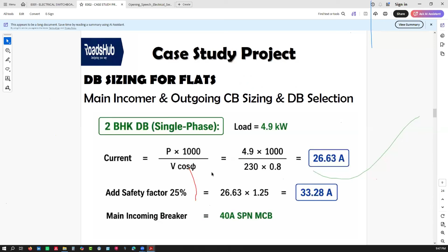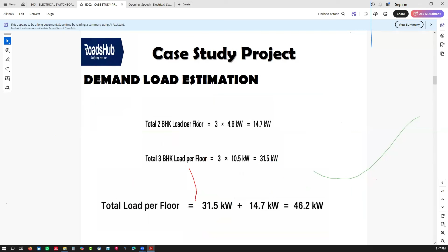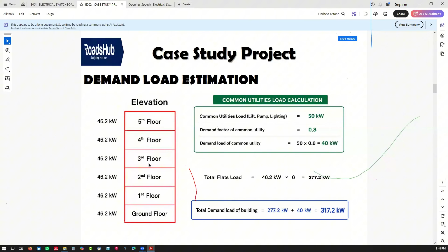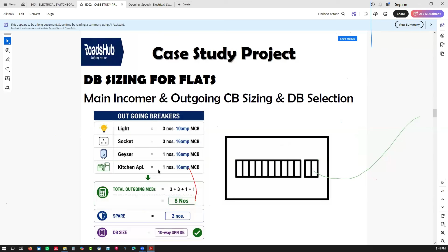So if I go now into the calculation of SMDB, simple. You need to know each floor is utilizing how much power. So you have 46.2 kilowatt per floor. And actually that's what we got here. 46.2 for each floor. So you need to design an SMDB for this floor, because remember you have first and fifth. They're actually far away from each other. You don't need a switchboard at first floor to supply fifth floor. It's not even practical. So each floor will have its own SMDB.